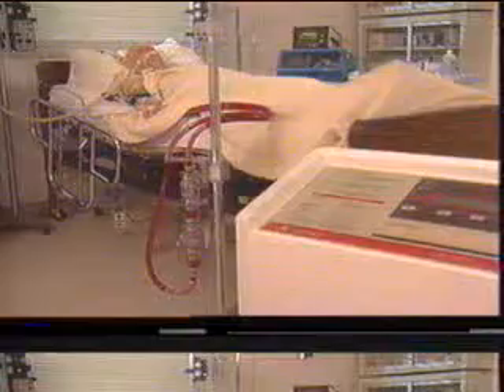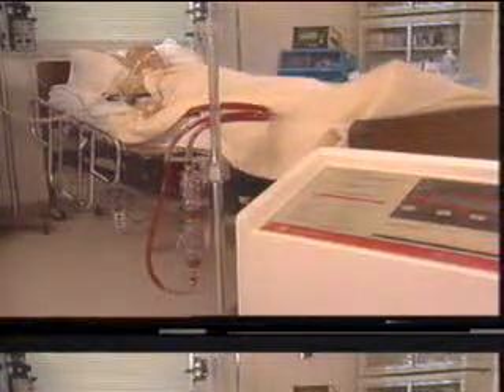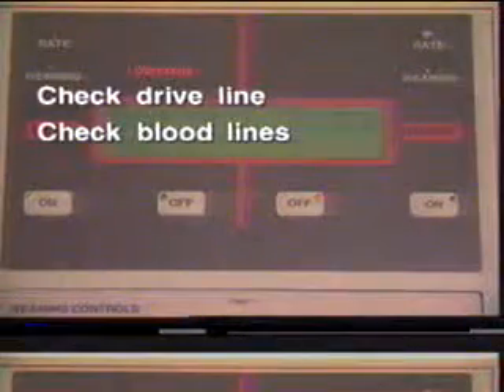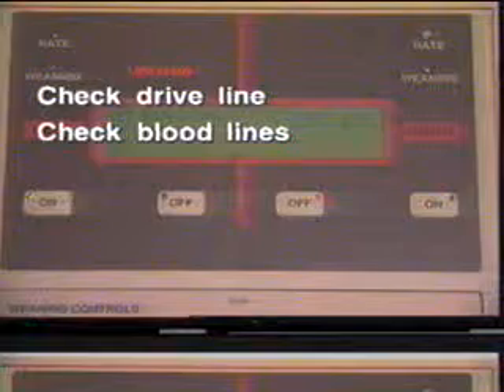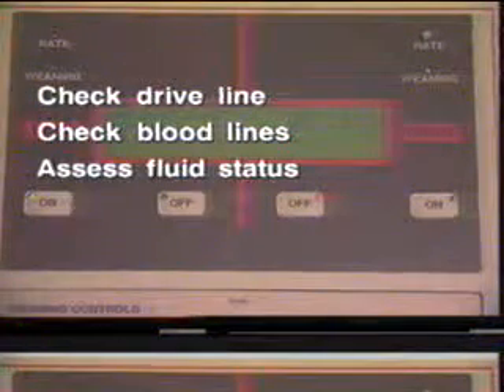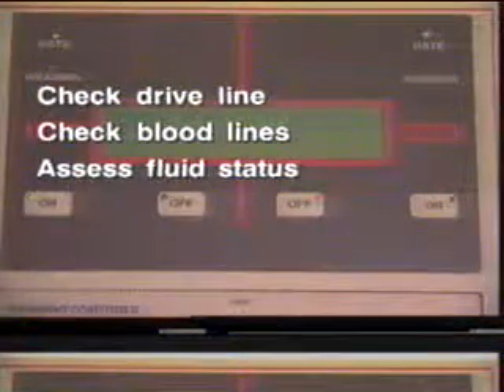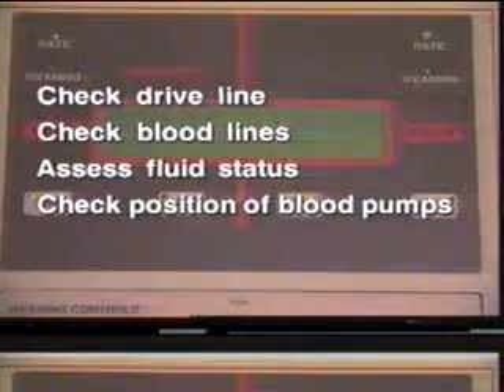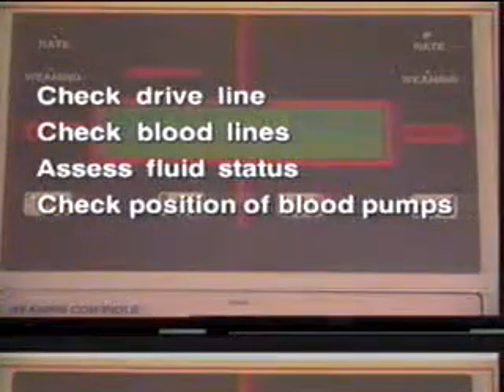The BVS console is extremely simple to operate and automatically adjusts blood pump beat rate and flow. If the console detects a significant decrease in flow, an audible alarm is sounded, and one of 3 messages is displayed on the console. The low flow alarm sounds whenever flow drops below 1.8 liters per minute in normal operation. Check the drive line and blood lines for kinking or obstruction. If flow is unobstructed, assess the patient for hypovolemia and ensure that the blood pumps are correctly positioned relative to the patient's atria.